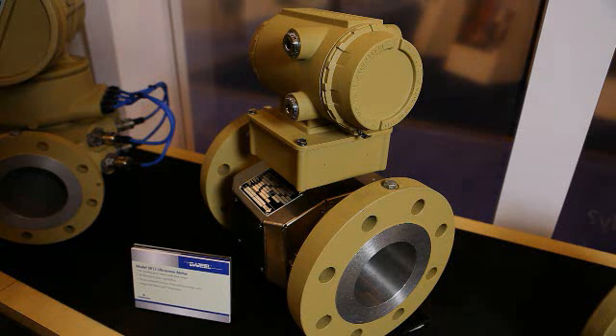So we can see that using the 3812 relative to a conventional PD meter allows us to go with a much smaller device. This much smaller device not only means a smaller diameter pipeline, but also means smaller valves, smaller ancillary equipment, smaller footprint, which are all critical factors, especially in offshore applications where space and weight are at a premium.